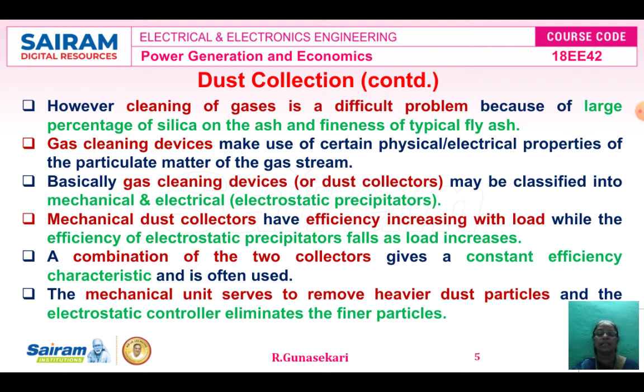The mechanical dust collector or gas cleaning device has higher efficiency with increase in load, but the electrostatic precipitator, that is the electrical dust collector, has its efficiency decrease with the increase in load. The combination of both collectors gives constant efficiency characteristics. The mechanical dust collector serves to remove heavier dust particles, but the electrical dust collector is used to eliminate the finer particles.